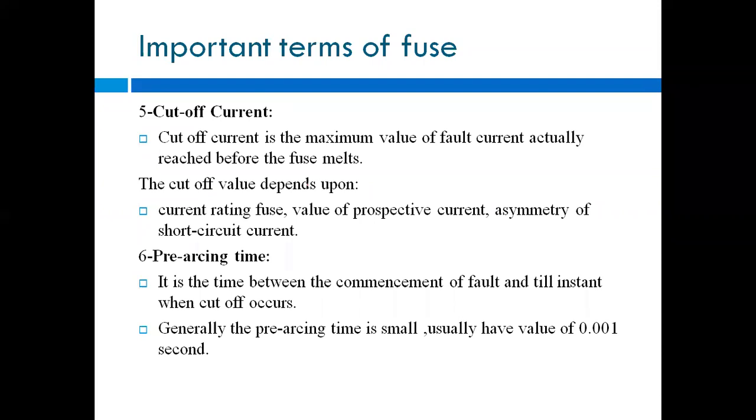Then the next term is the pre-arcing time. So what is this pre-arcing time? Pre-arcing means it is below the maximum level, or less than that cutoff current. It is the time between the commencement of the fault and the instant when cutoff occurs. It means when any fault occurs, at that instant your fuse is not melting.